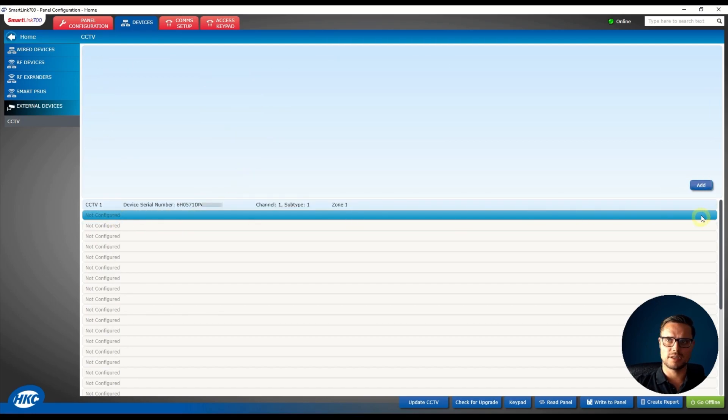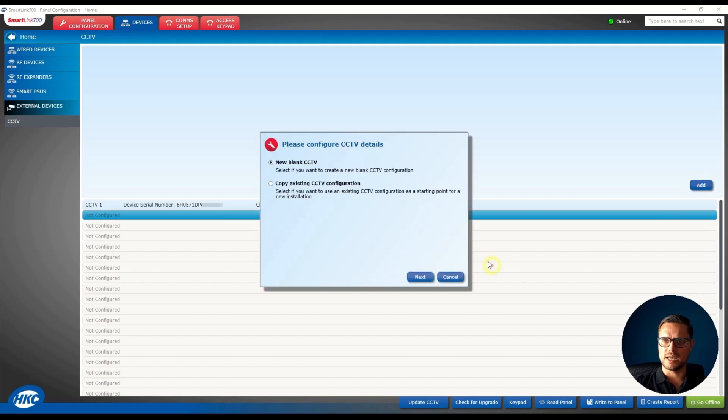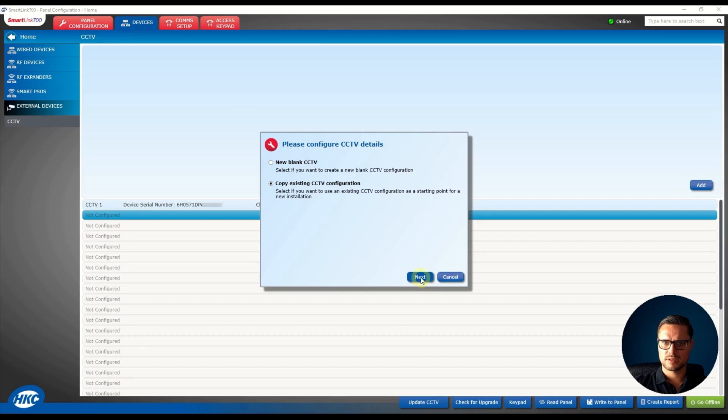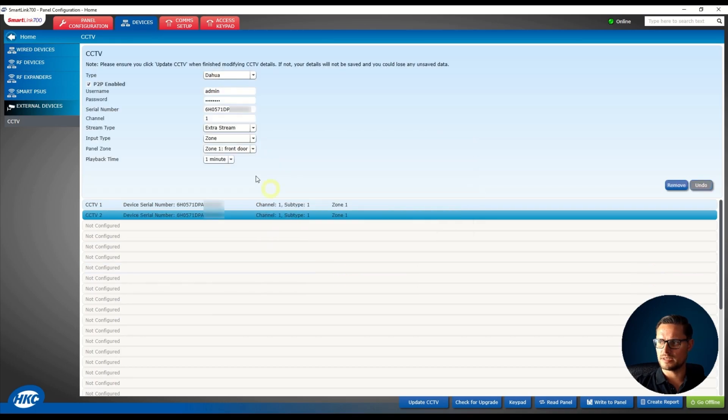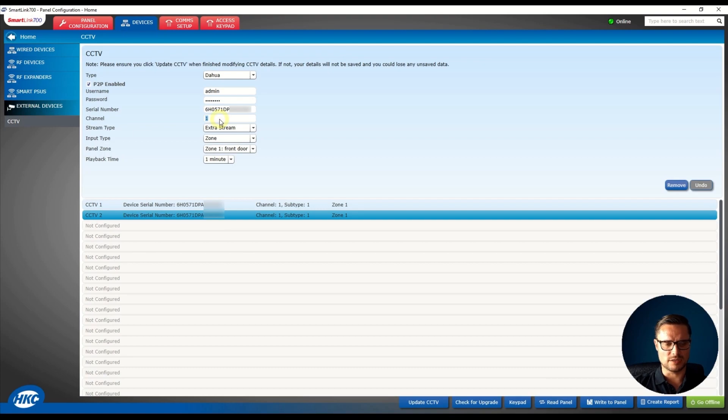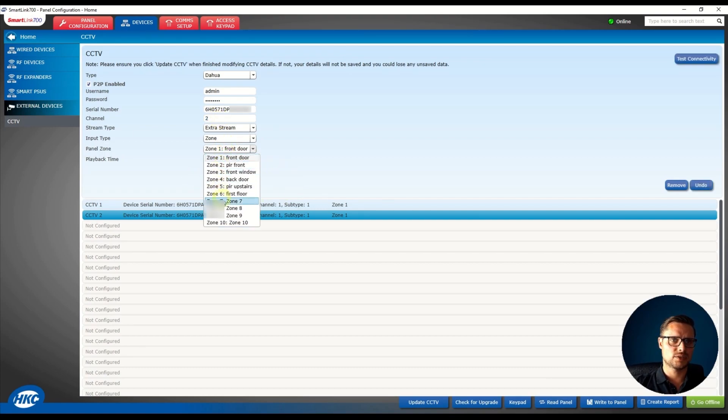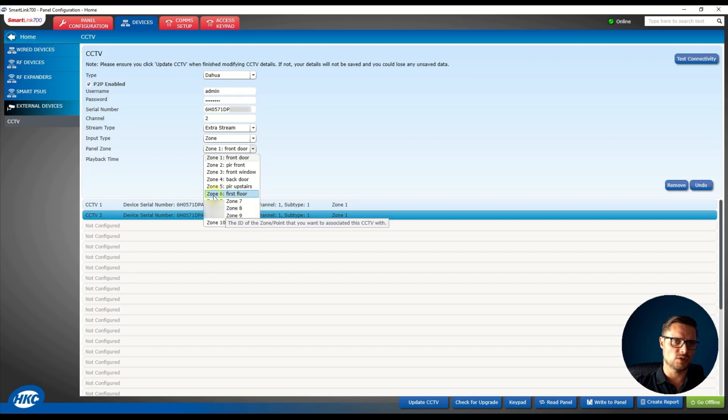And just copy the existing site information, the only thing that I need is to change the channel number to number two and link that to a different zone so my second zone could be the first floor and the second channel of my recorder.